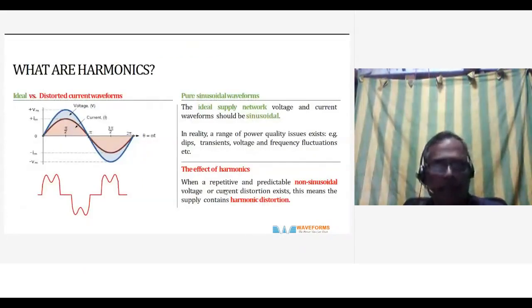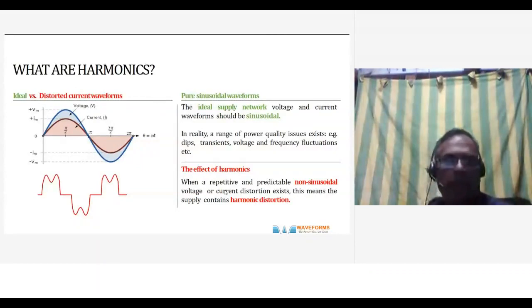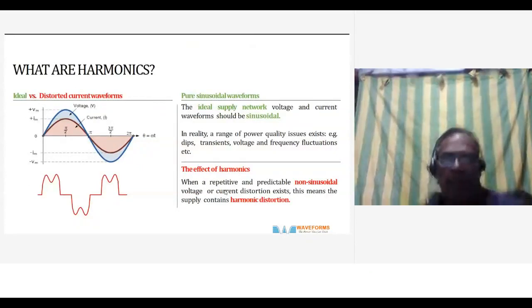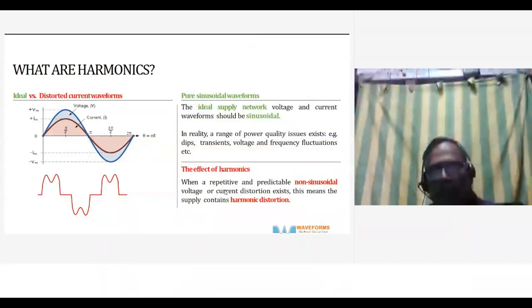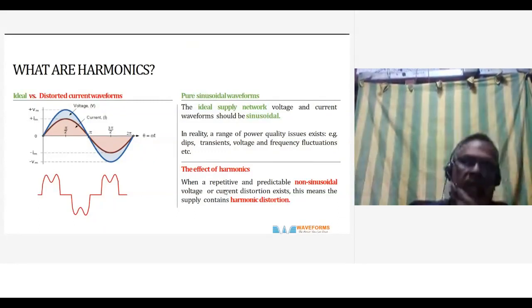So this is a pure sinusoidal waveform, and it is the ideal supply. But in reality, it is not there because of these non-linear loads. When a repetitive and predictable non-sinusoidal voltage or current distortion exists, this means the supply contains harmonic distortion. So this is a typical distortion that you see in red in three-phase drives.